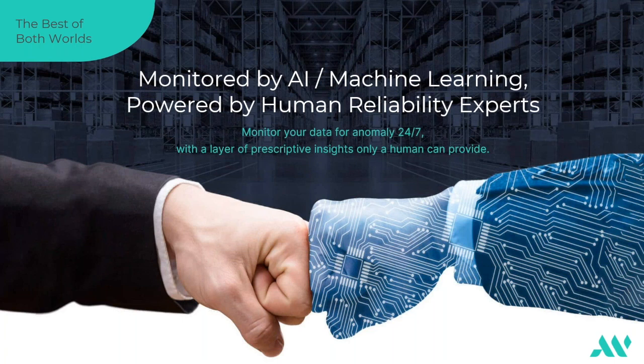And what we end up finding out is he's just always done it one way. He's convinced that will always work. Well, we got that to higher up team members in a very polite manner. And guess what he got for Christmas? A laser alignment tool. Guess what issue that plant hasn't had in 4 months that they had 8 issues of last year? They have not had a coupling go out. So that's one of those great examples of how that human element is so very important, even though the technologies come in leaps and bounds.